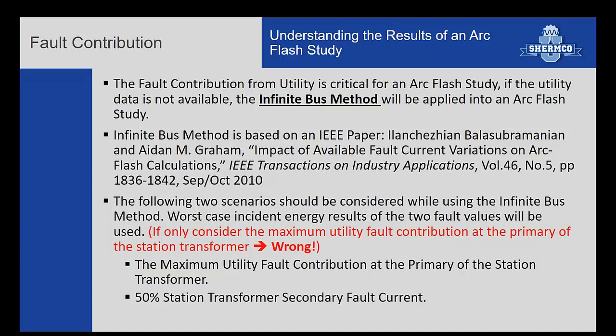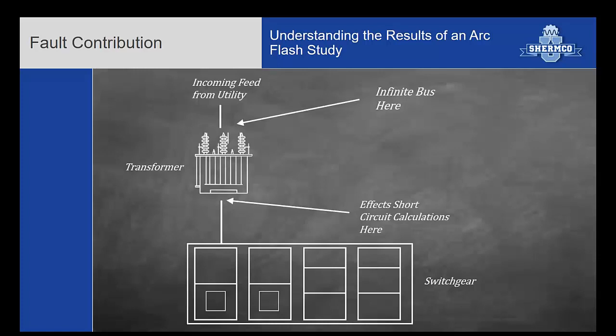There's a paper put out by IEEE where you use the maximum fault current and then you use 50% of the station transformer current. So if your maximum current, if the utility won't give you good information, if you assume maximum current here, the more into this transformer, the more you're going to get out. If you don't have maximum current, you're not necessarily going to have that coming out of the transformer. So if you assume infinite bus, it might throw all your arc flash readings off. So this paper recommends, and most standard engineering software allows you to select this option where you do 2 points. You do infinite bus, and then you do 50% of that, and then you get the worst case, and that's what you use for your arc flash study. So it's just one more thing.